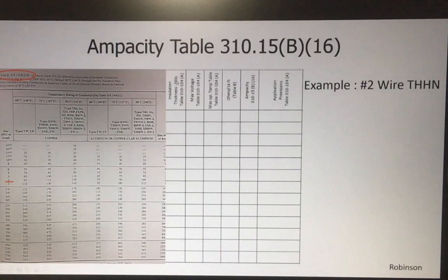And then your ampacities, when you do the ampacities, use the 60-degree column. The 90-degree column ampacities are strictly for wire derating purposes only, because it's kind of like if you have a chain, let's say, and every link on the chain is rated for 1,000 pounds, but one link is only rated for 500.